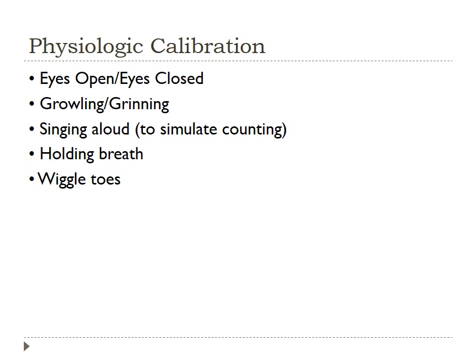Your physiological calibration is going to be done with pediatrics just like you would with adults. However, you might need to make some modifications. You can instruct the same eyes open and eyes closed based on the child's age, if they can follow those kinds of commands. But you might have the child growl or grin to see the chin EMG, or have the patient sing aloud to simulate counting. You can ask them to hold their breath or wiggle their toes — it's brought down to the child's level and made into a game for them, unlike adults where you just tell them what to do.